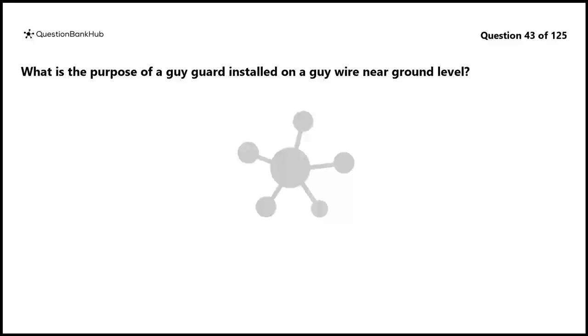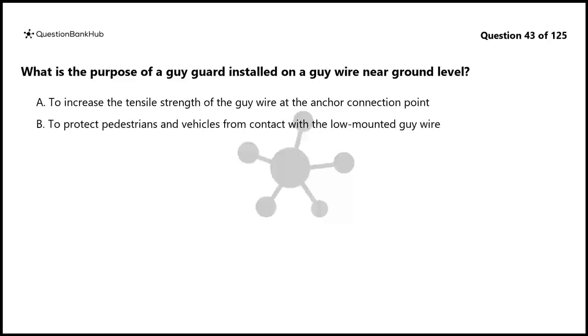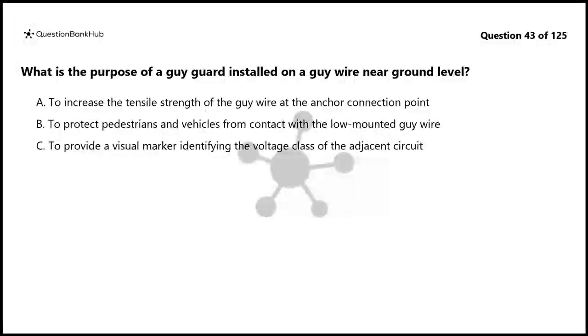Question 43. What is the purpose of a guy guard installed on a guy wire near ground level? A. To increase the tensile strength of the guy wire at the anchor connection point. B. To protect pedestrians and vehicles from contact with the low-mounted guy wire. C. To provide a visual marker identifying the voltage class of the adjacent circuit. D. To prevent galvanic corrosion of the guy strand at the soil transition zone.